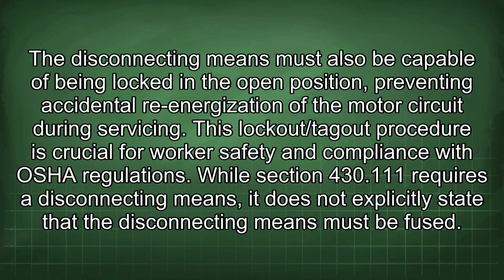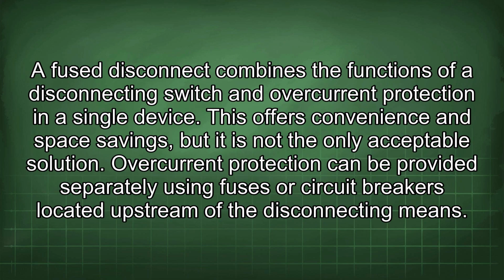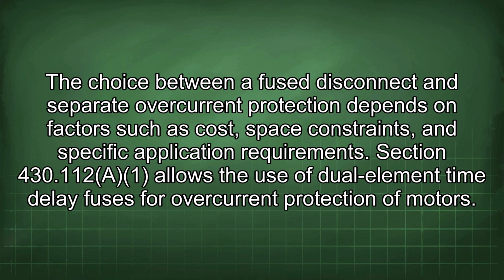While Section 430.111 requires a disconnecting means, it does not explicitly state that the disconnecting means must be fused. A fused disconnect combines the functions of a disconnecting switch and overcurrent protection in a single device. This offers convenience and space savings, but it is not the only acceptable solution. Overcurrent protection can be provided separately using fuses or circuit breakers located upstream of the disconnecting means. The choice between a fused disconnect and separate overcurrent protection depends on factors such as cost, space constraints, and specific application requirements.